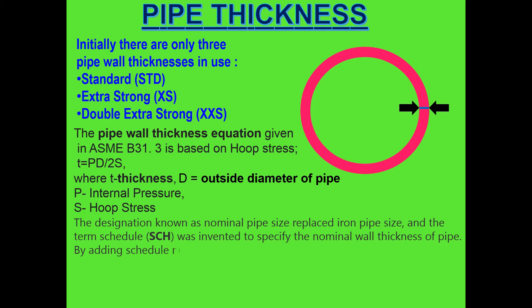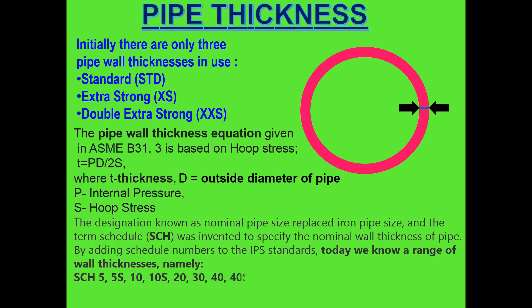The term schedule (SCH) was invented to specify the nominal wall thickness of pipe. By adding schedule numbers to the IPS standards, today we know a range of wall thicknesses, namely: SCH 5, 5S, 10, 10S, 20, 30, 40, 40S, 60, 80, 80S, 100, 120, 140, 160, STD, XS, and double XS.